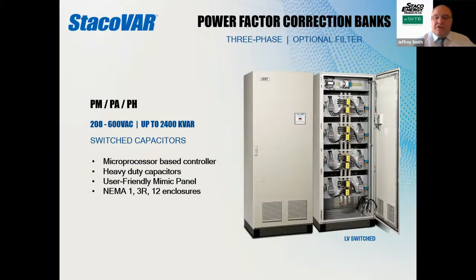This is what the power factor correction that Staco offers looks like. You can see there are different steps in these sections. Depending on how many kVARs we have to add in to bring your power factor up to the levels that you're looking for, we put in different steps, depending on what's going on in your facility. You have motors turn on for, let's say, air conditioning. All of a sudden, your power factor goes very bad. We add in another step of capacitors, and boom, it brings it right back up to where it gives you good levels. We can do it in NEMA 1 enclosures. That's our standard, but we do a lot of these systems with NEMA 3R, NEMA 12, even NEMA 4X. Next slide.